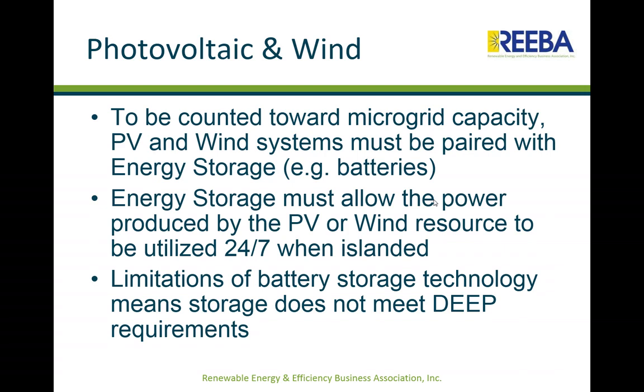Focusing on photovoltaic and wind first: under the rules, to be counted towards the microgrid capacity, PV and wind must be paired with energy storage, for example battery storage. However, that battery storage must be able to be utilized 24/7 when islanded. As you probably know, and hopefully I'll be corrected during the storage presentation, there are current limitations on battery storage technology, and we're not sure if it's economically feasible for batteries to run 24/7 when islanded.